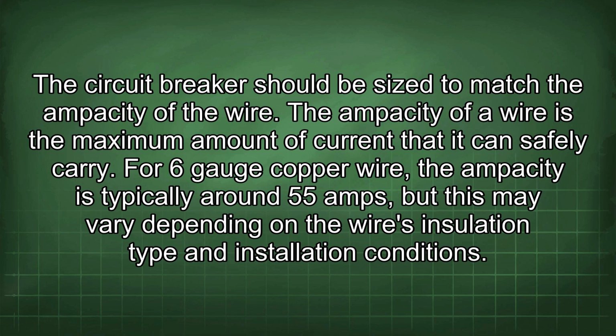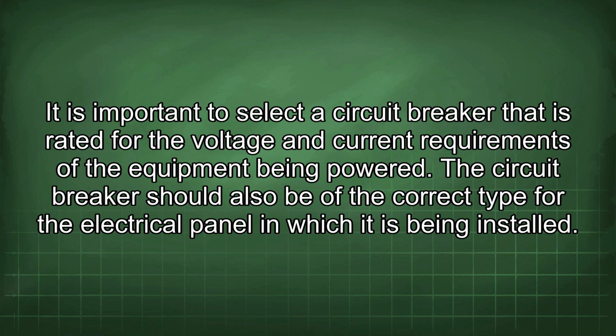The ampacity of a wire is the maximum amount of current that it can safely carry. For 6-gauge copper wire, the ampacity is typically around 55 amps, but this may vary depending on the wire's insulation type and installation conditions. It is important to select a circuit breaker that is rated for the voltage and current requirements of the equipment being powered. The circuit breaker should also be of the correct type for the electrical panel in which it is being installed.